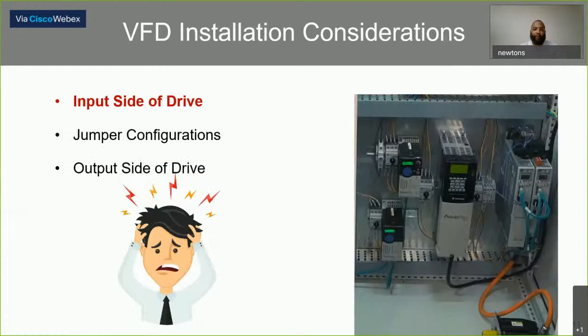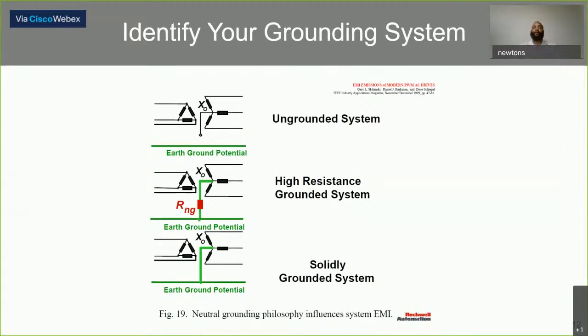So let's start off with the input side of the drive. The first thing that you need to do, which is extremely important when designing your power system and installing these variable frequency drives, is to identify your ground system. This can be identified by looking at your single line diagram. Typically the most common grounding systems or power systems would be an ungrounded system, a high resistance ground system, or a solidly grounded system. And in the VFD world, we really want a solidly grounded system.